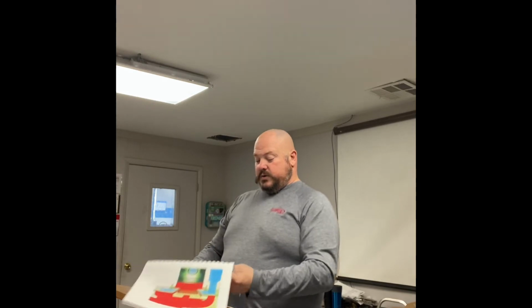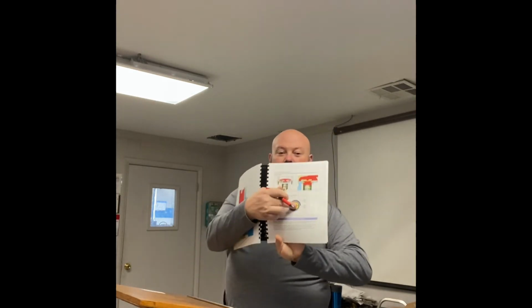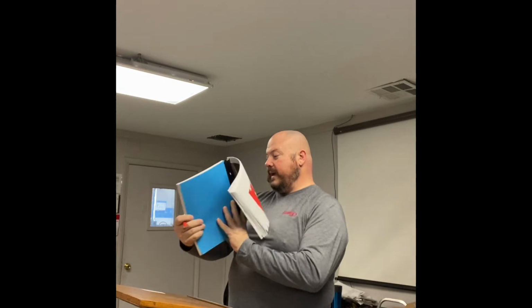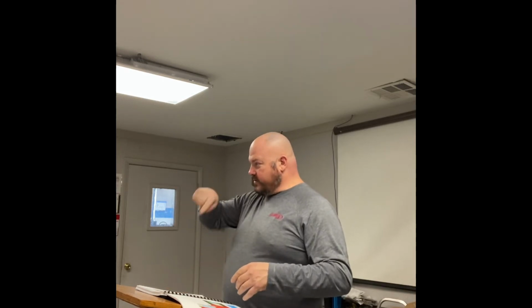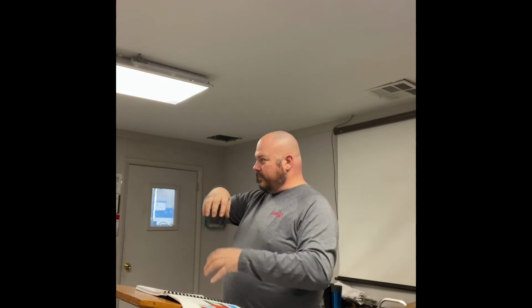The very next page has this little squirrely thing at the bottom here. That is reciprocating or a scroll compressor. Okay? Basically, you have a positive and negative image, just like a mold. Okay? You got one that screws one way and one screws the other way. They fit inside of each other. One is firmly mounted and doesn't move. The other one is moved on the shaft, mounted on the shaft of the electric motor, and it oscillates.